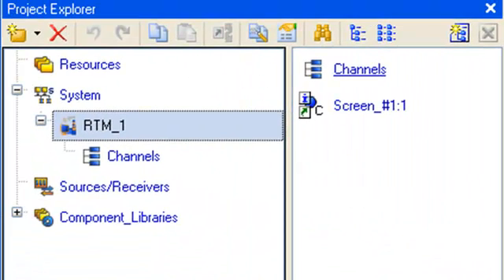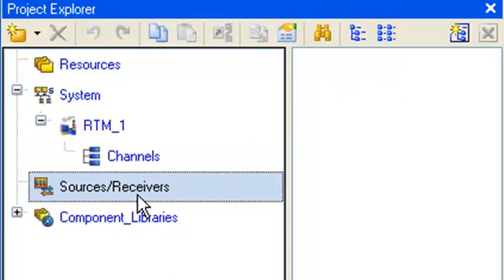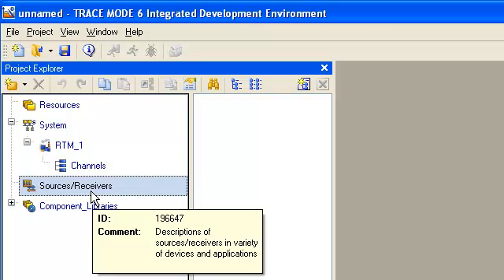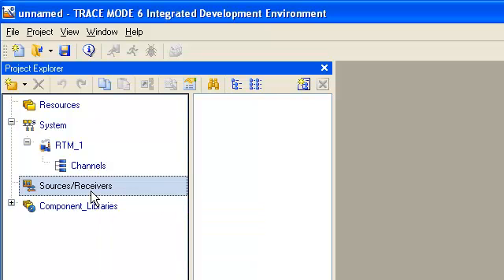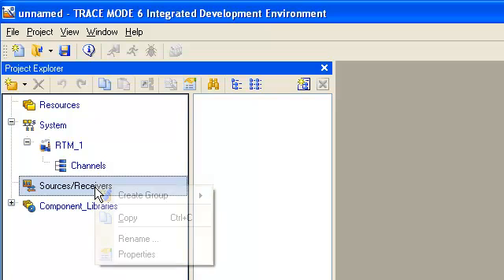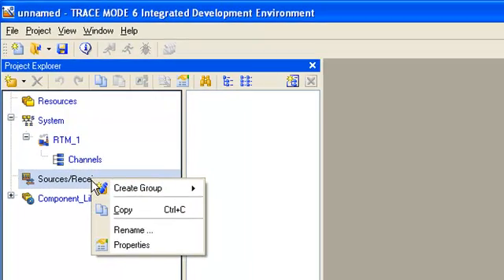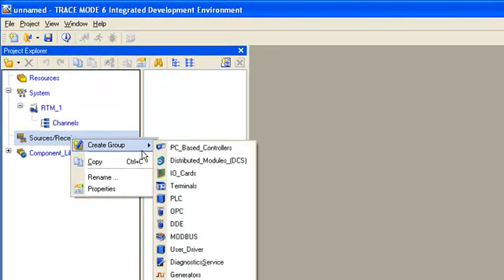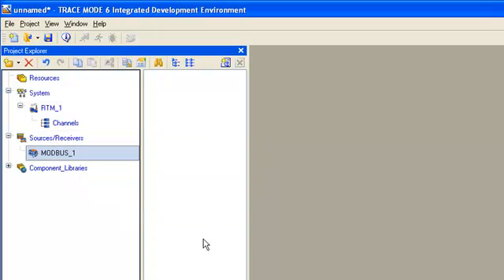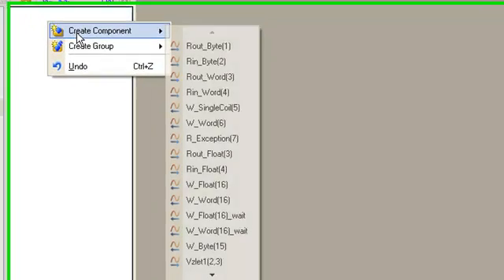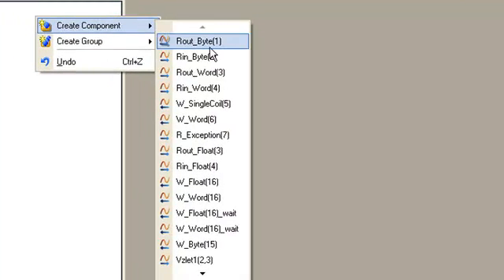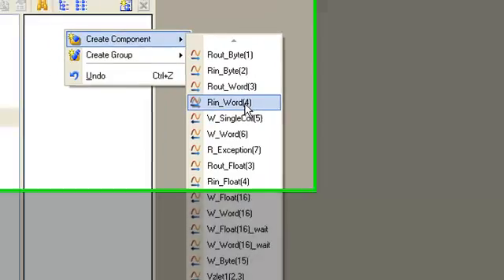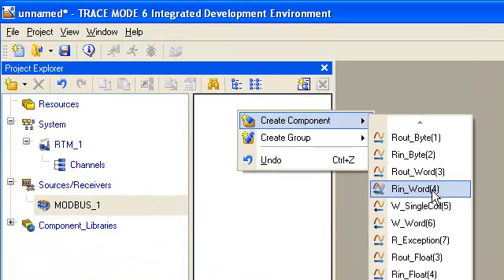Let's start our project development from the layer sources/receivers, where we describe input register inside ModBus RTU device. For that, we open the menu using the right mouse button and select the group ModBus. In this group, we create a new component RINWORD4 because we need to use the ModBus command number 4 for reading the input register.